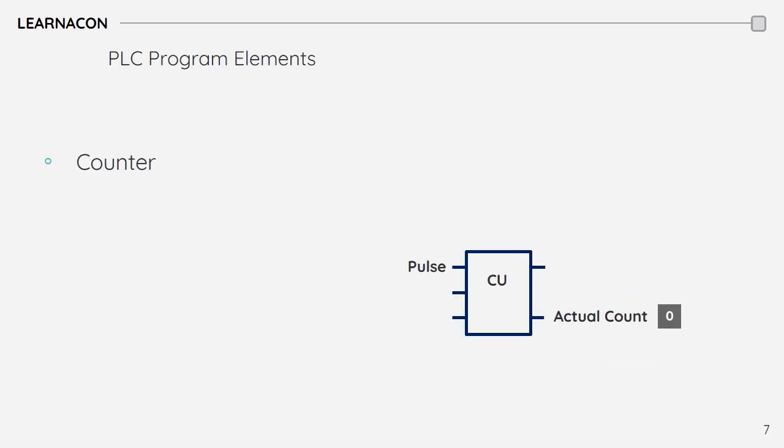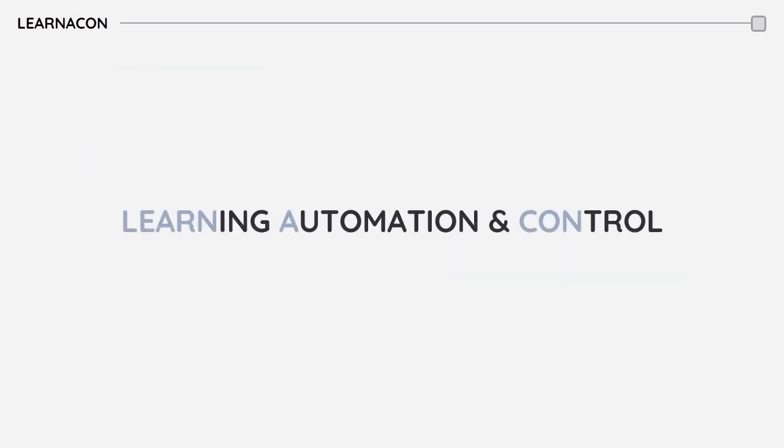You can configure a counter to latch an output when it counts to a preset number. This scenario is used a lot in production machines. For example, in the packaging machine below, we want to activate the boxing process when 4 products are in the packing area. We preset our counter with 4 as the set point. The proximity sensor that detects the products is connected to the counter input.